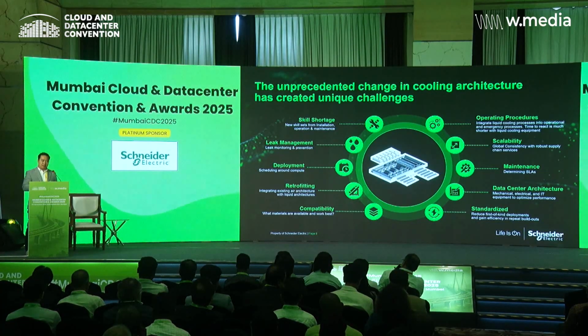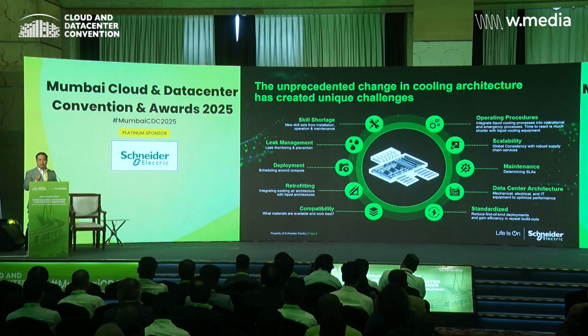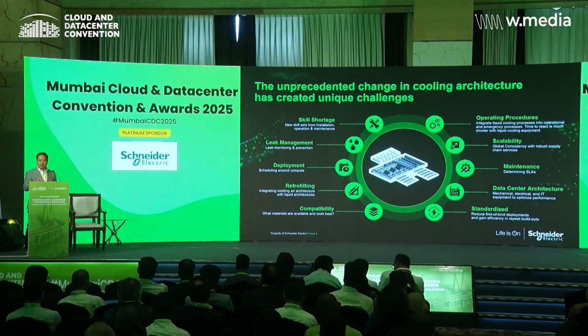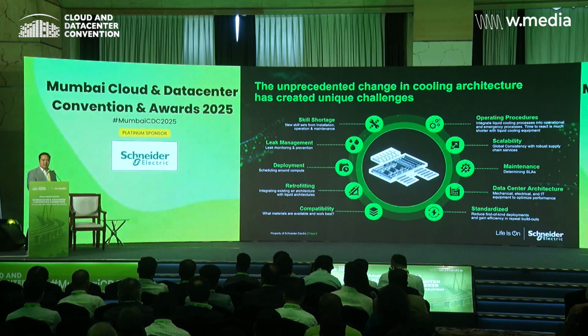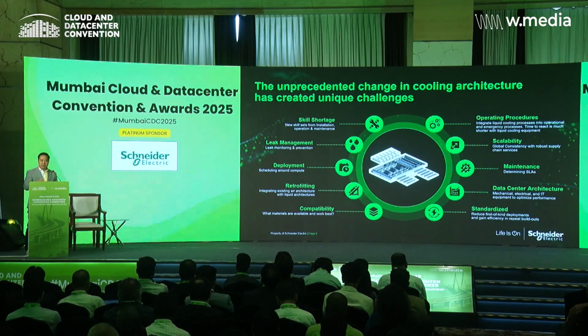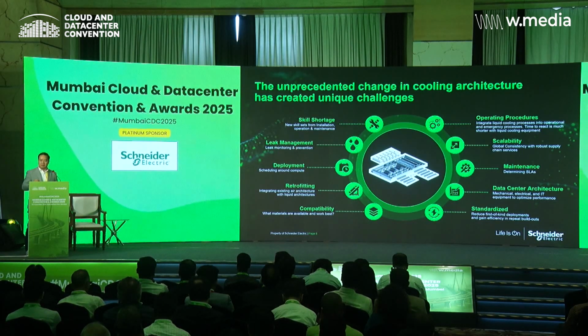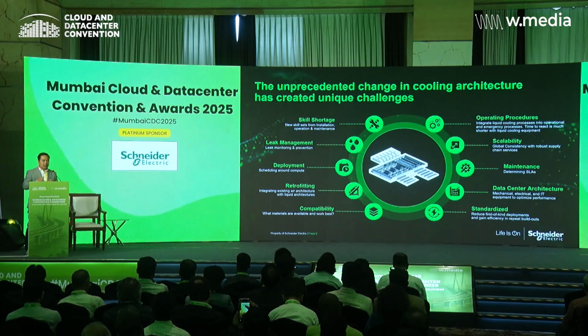And if you want to scale, to deploy at scale, you really have to think about what's available in the supply chain. A lot of the piping and piping accessories that meet the criteria for wetted material on the TCS loop really have limitations on size. Readily available, you're talking 300 millimeters or less, 150 millimeters or less. Beyond that, the valves and accessories all get harder and harder to get, and it's not readily available.